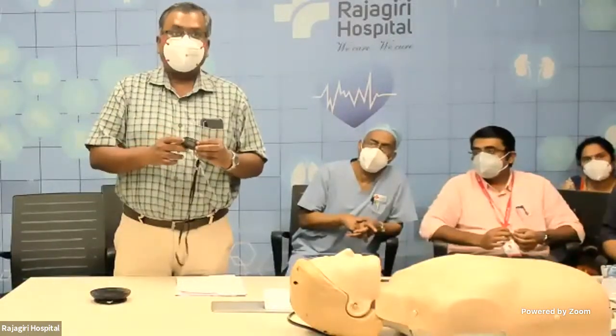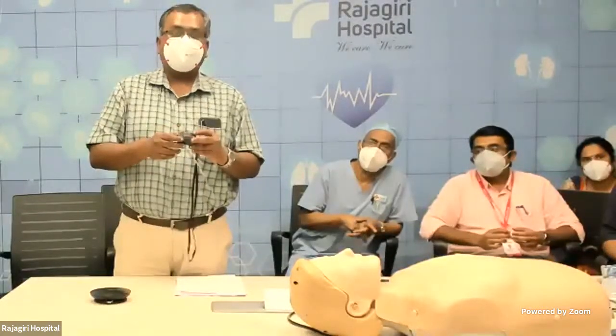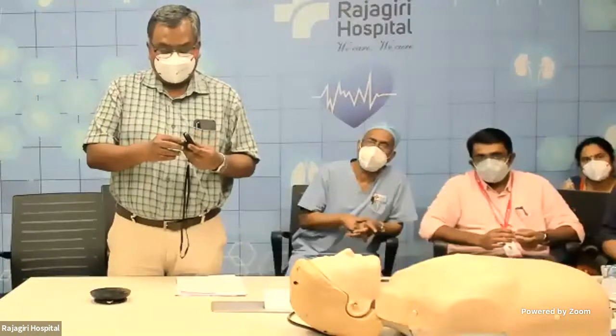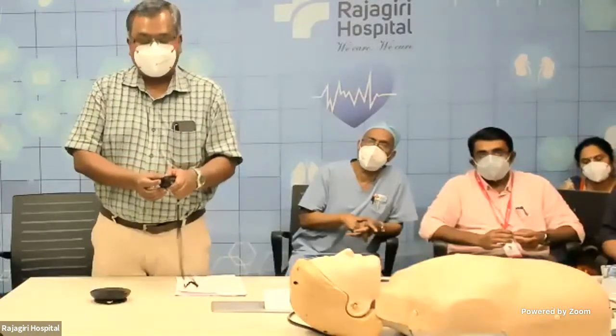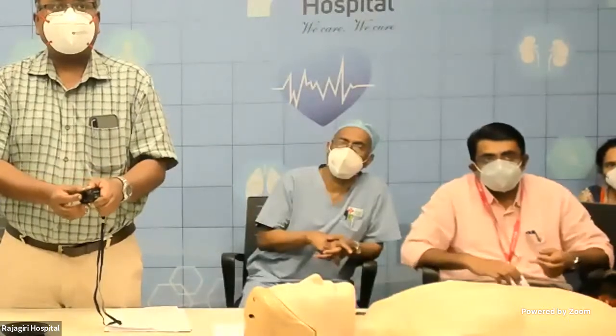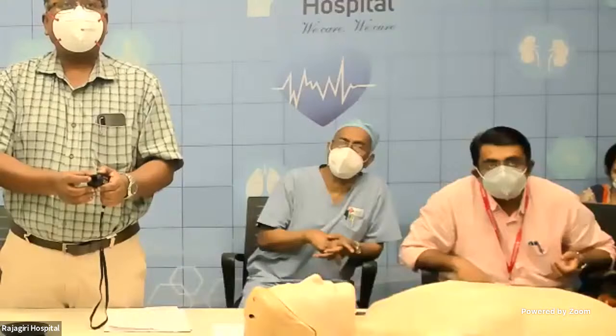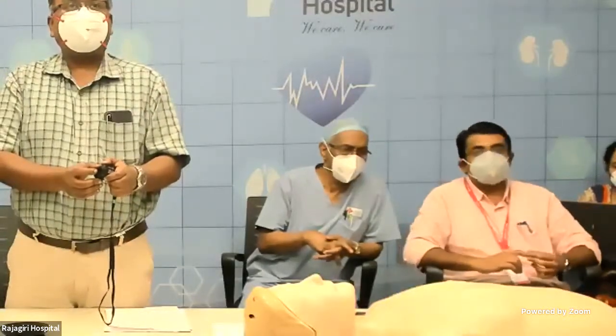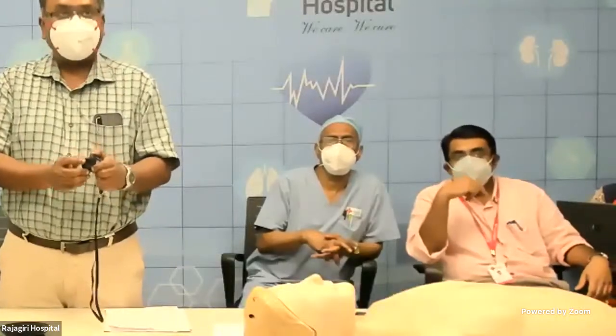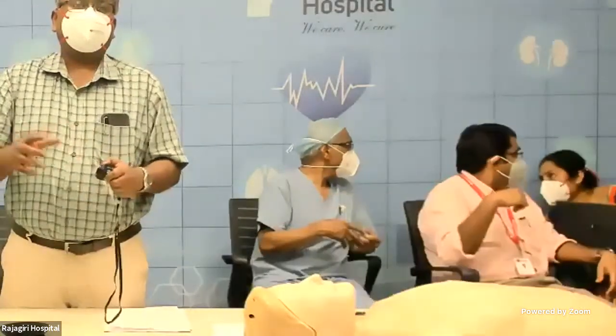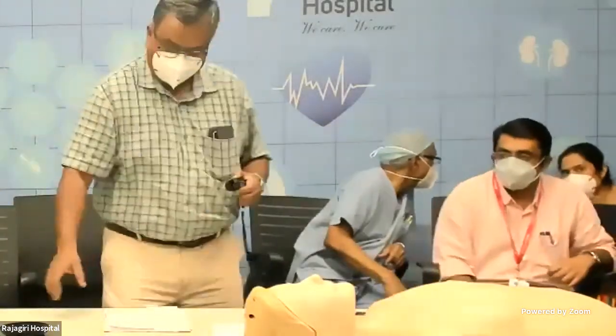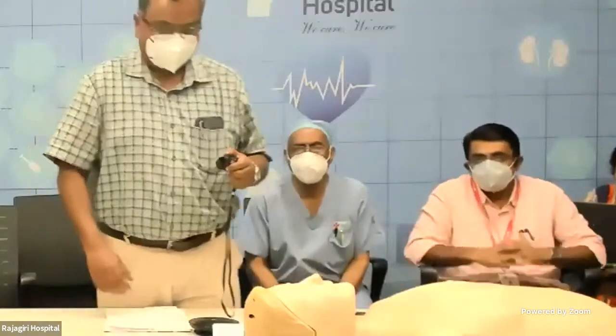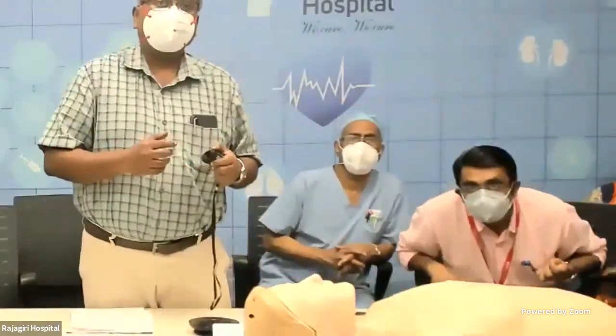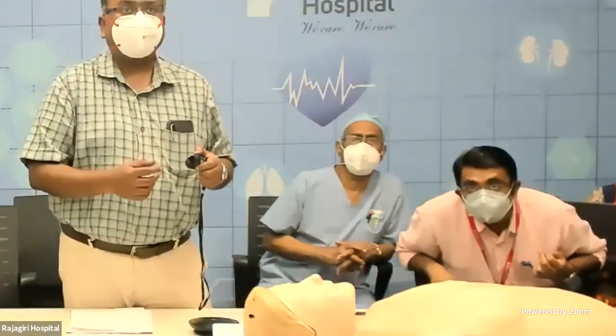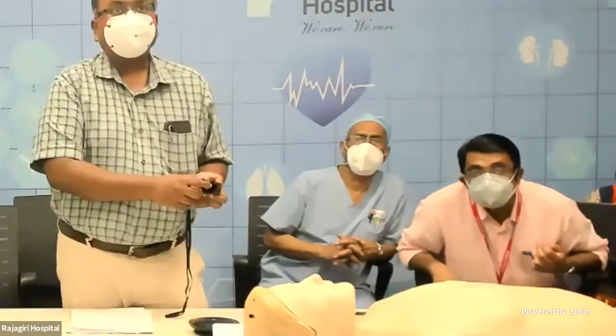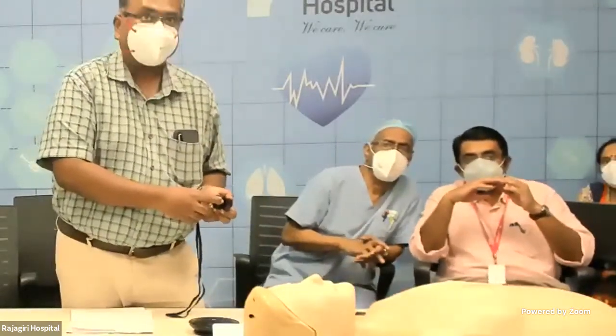This device works on a complicated principle called the Beer-Lambert law. I'm not going into the details of that, but it just tells you there is a light emitting diode. I am sure you will be able to see that. There is a light emitting diode which emits light in two frequencies. One is in the infrared frequency and the other diode emits in the red ray. Now, when this ray of light passes through the body tissue and reaches a detector on the other side of the pulse oximeter.